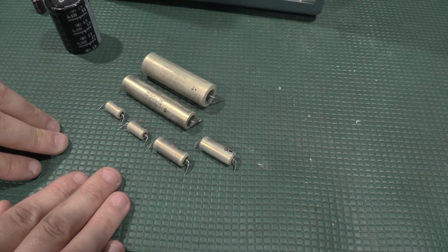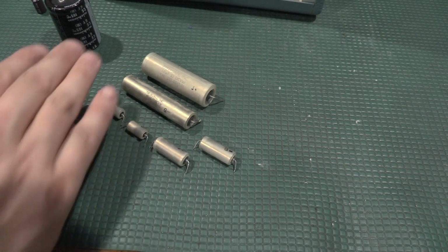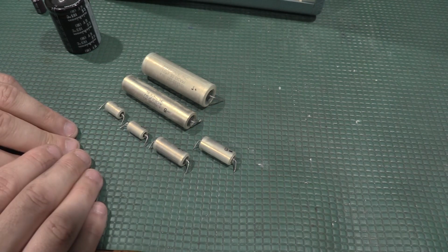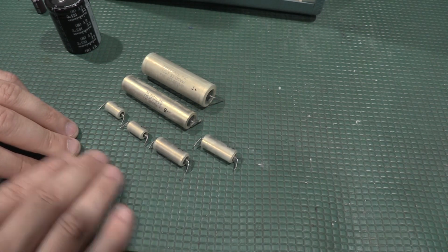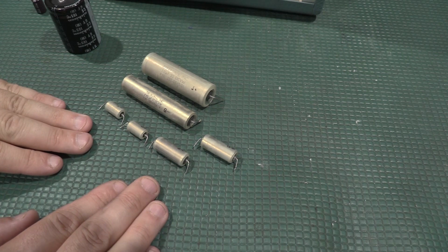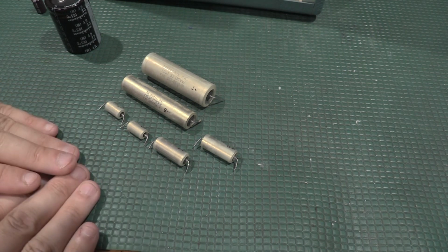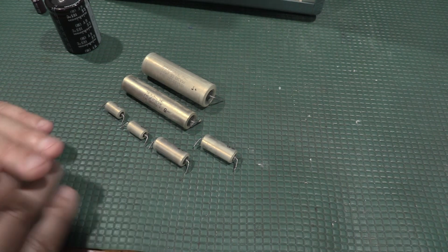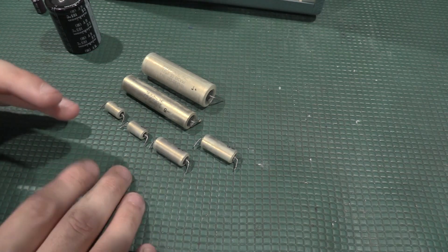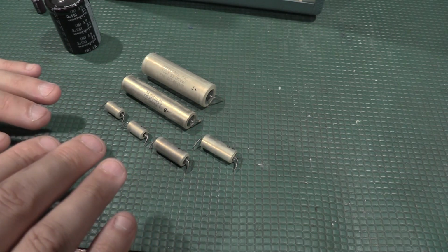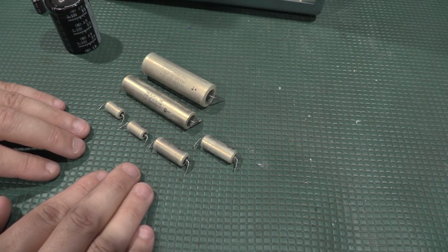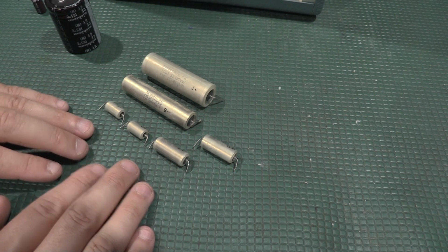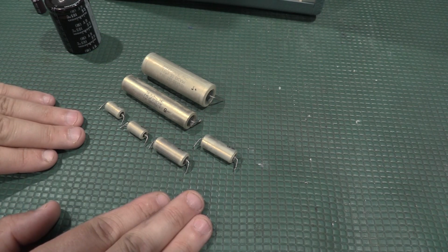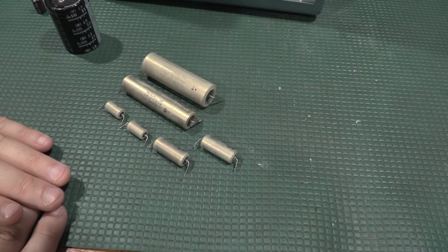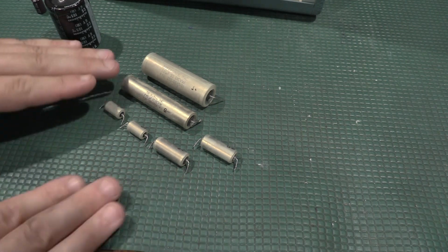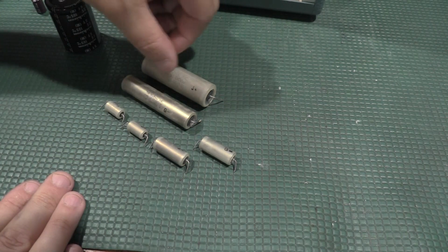You can't buy one of these caps individually. If one of these caps failed, you replaced all of them in the scope to make the front dial work correctly with the A and B sweeps. So if you're working on a 400 series scope or a 7000 series, well, any scope really, the timing caps, unless they are proven bad, leave them alone.